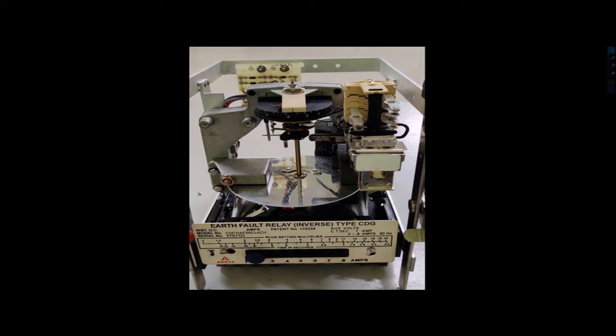Now, this is the construction of the electromechanical type relay, and for example, we are taking an earth fault relay. Now, let's see what components are used in this relay. This is the nameplate of the relay. This one is called the plug setting of the relay. Here, different plug settings are available according to the settings of the relay. Here, it is starting from 0.8, for example. That plug setting is used for the earth fault relay.